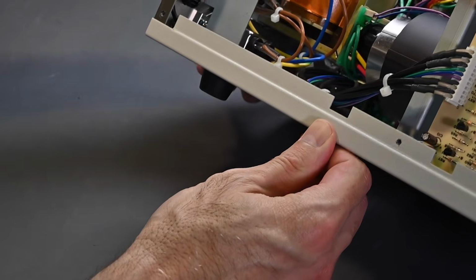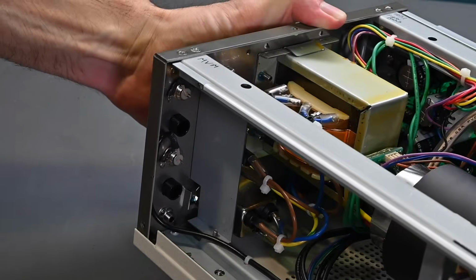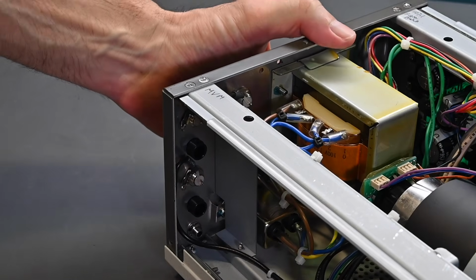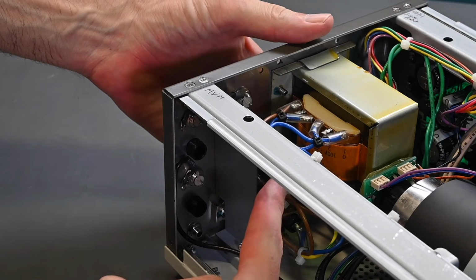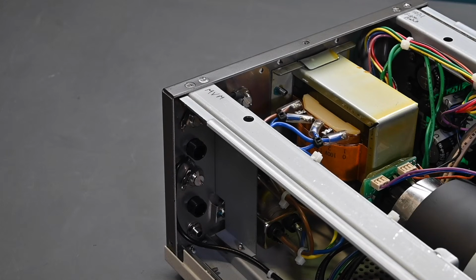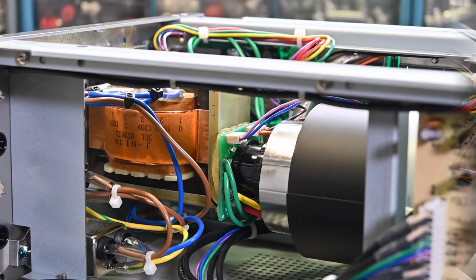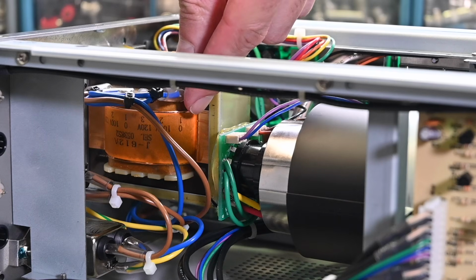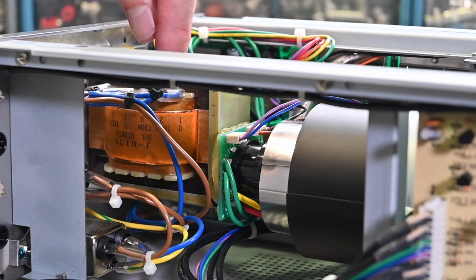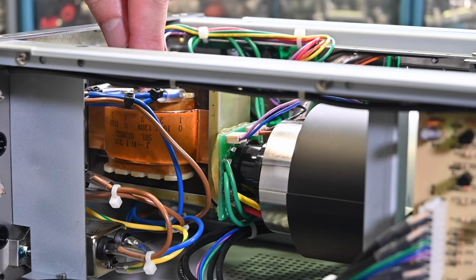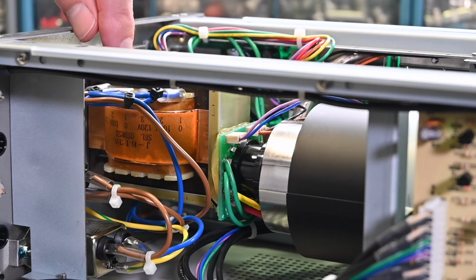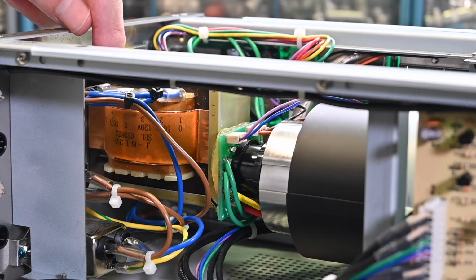So it looks like, this is really awkward to see down in there with the camera. Let me get the camera positioned a little bit better, and you can see down in here. We'll take a look at those taps. All right, so it looks like the transformer has two primary windings. It starts over here at the bottom end of this winding. It's marked as 0. Then the next tap is 100, and then the next tap is 120. Then it repeats again. It's 0, 100, and 120.